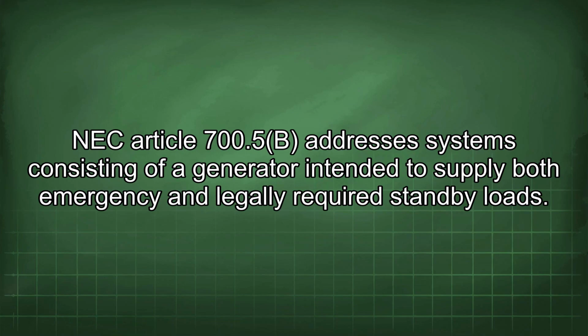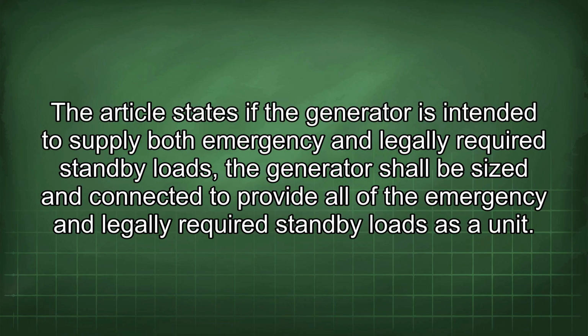NEC Article 700.5(b) addresses systems consisting of a generator intended to supply both emergency and legally required standby loads. The article states if the generator is intended to supply both emergency and legally required standby loads, the generator shall be sized and connected to provide all of the emergency and legally required standby loads as a unit.